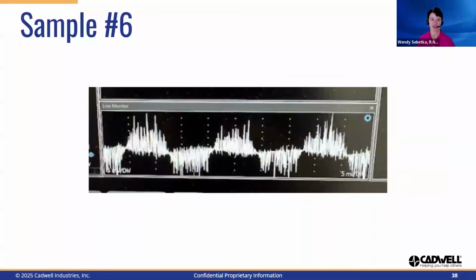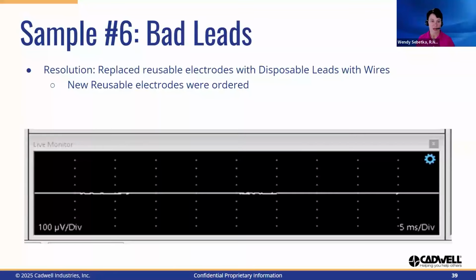Sample number 6 just started today. Key points of this waveform note spiky, sinusoidal, consistent waves. Looking at the sample, I'm comfortable assuming this is coming from a non-physiological source. Further investigation determined a reusable electrode that had not been replaced in several months or even years. Electrode management troubleshooting techniques were implemented and the old reusable electrodes were replaced with disposable electrodes with wire and the issue was resolved. When using disposable tab electrodes, you should also remember to replace the alligator clips frequently as well.